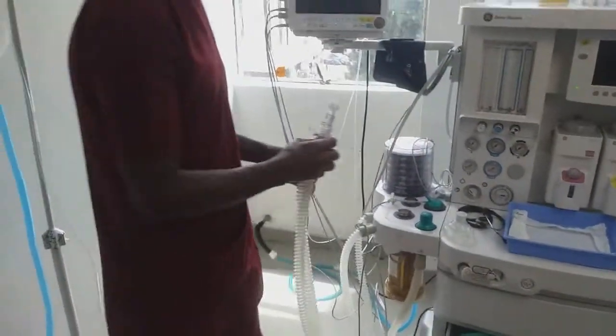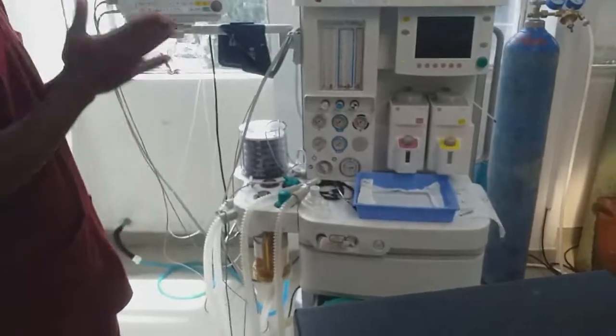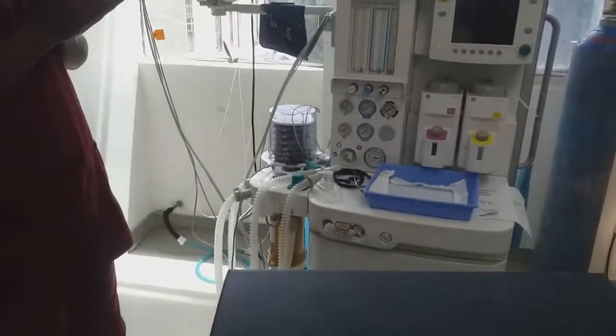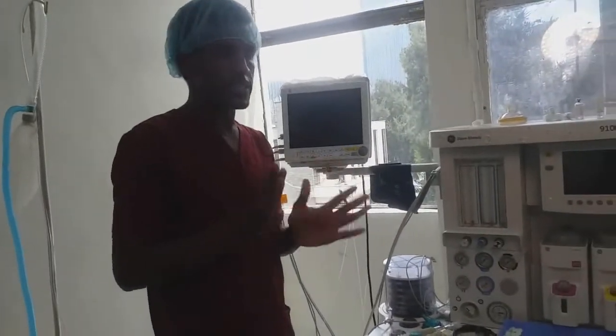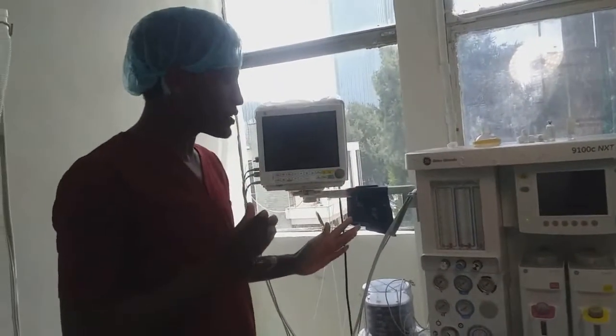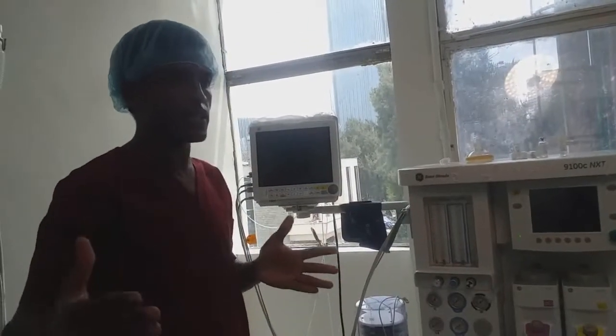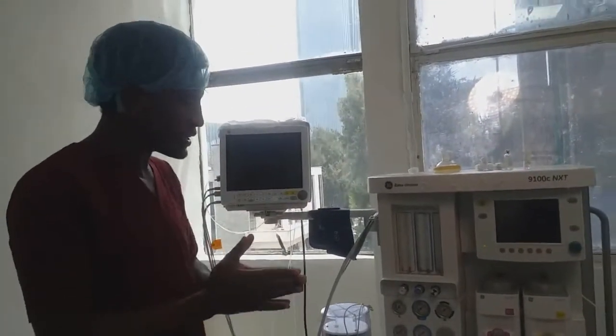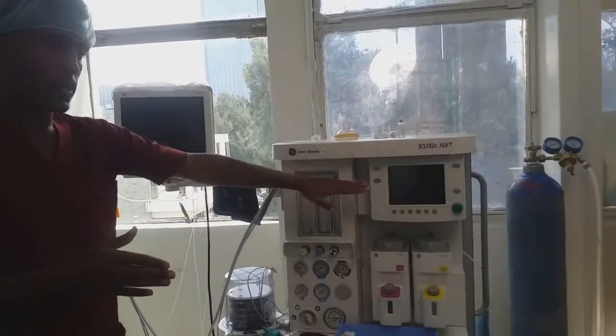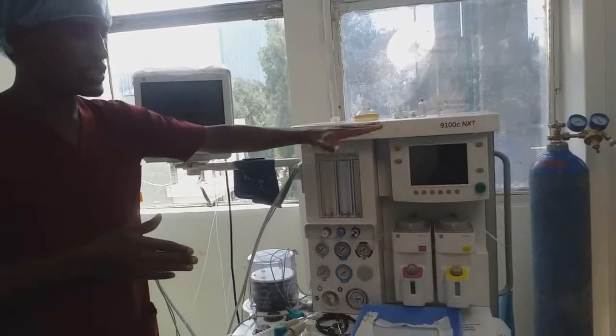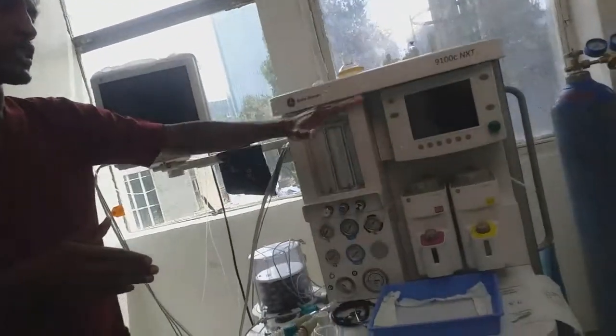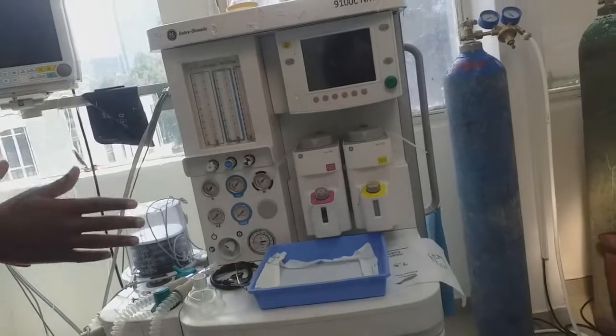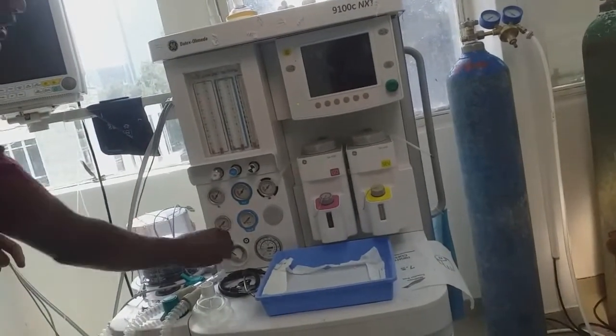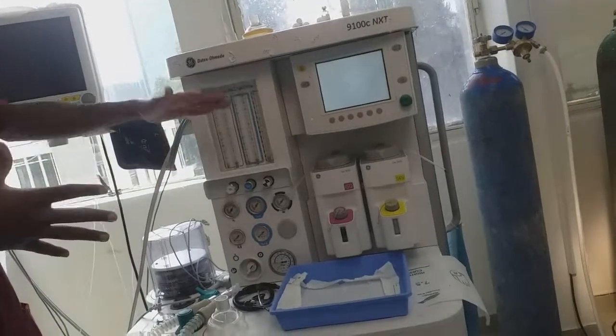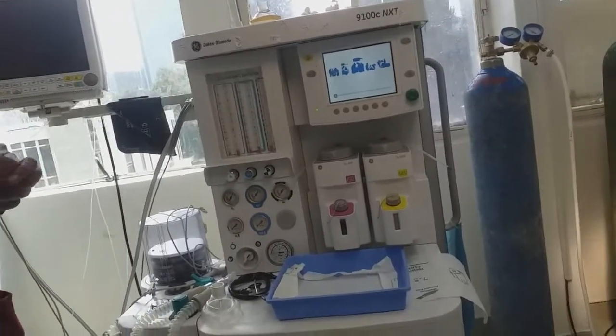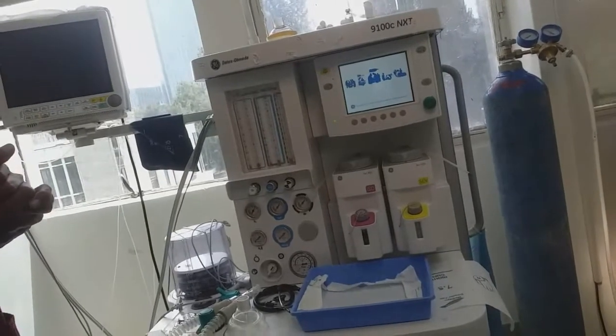Now I'm going to check the low pressure system leak. We can check the low pressure system in two ways. The first one is manual, and the second one, if there is a suction bulb, is to check with the suction bulb. When we check with the suction bulb, the machine is in the off position. But if we check manually, the machine should be on. Now I'm going to turn on the machine to check the low pressure system leak. Now the machine should be on.